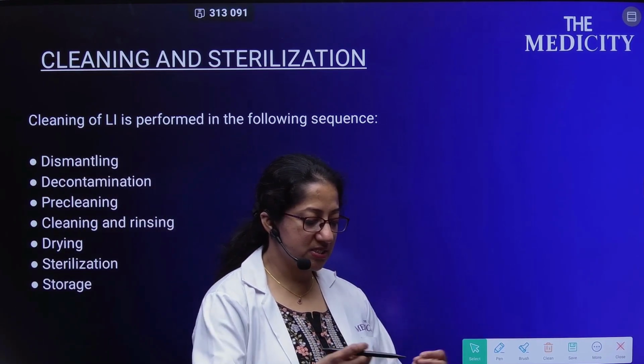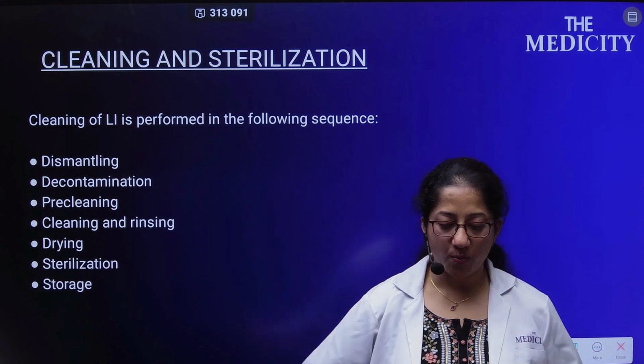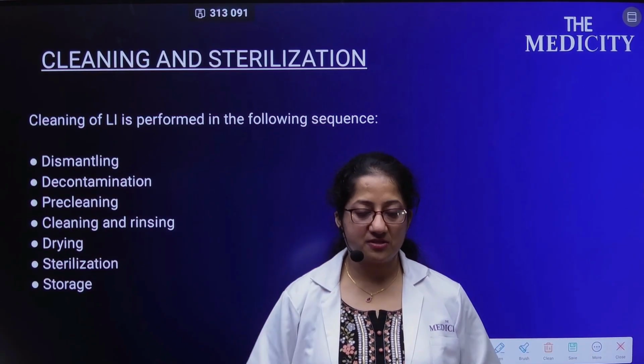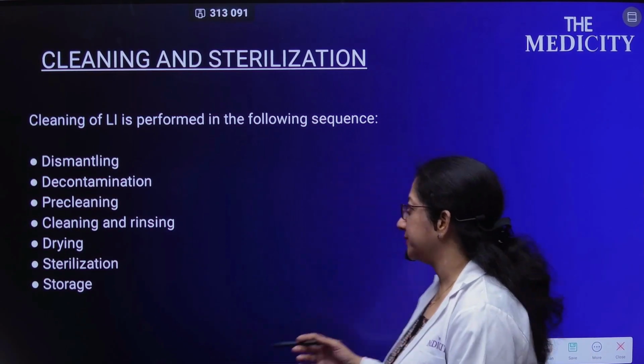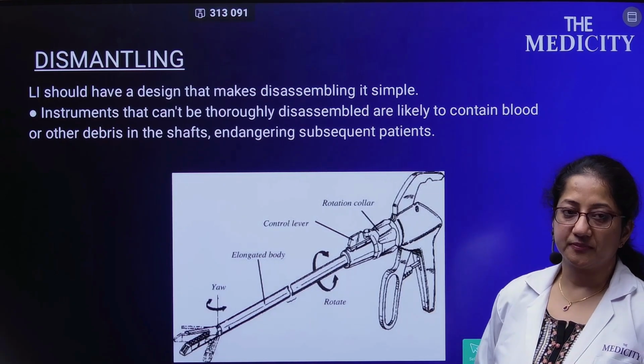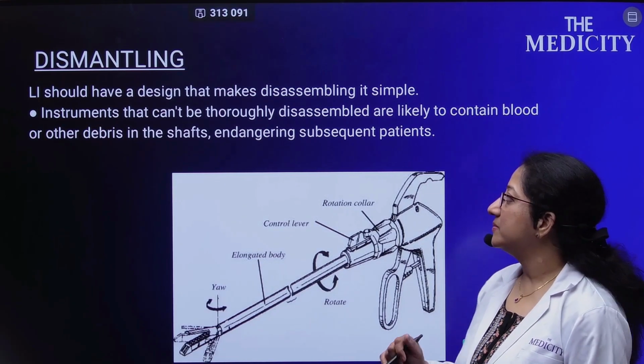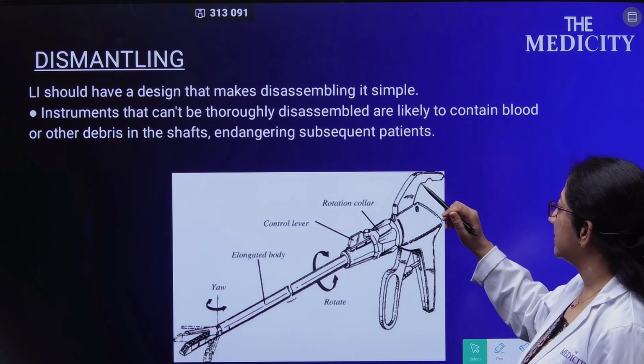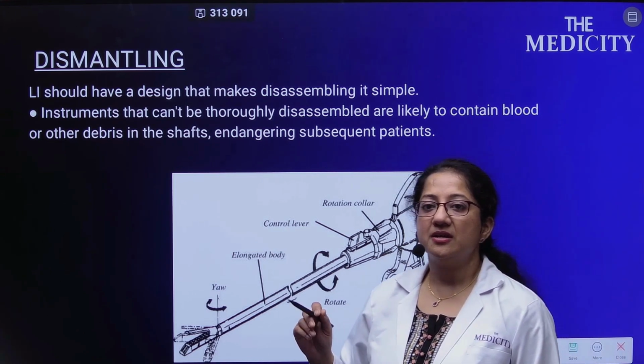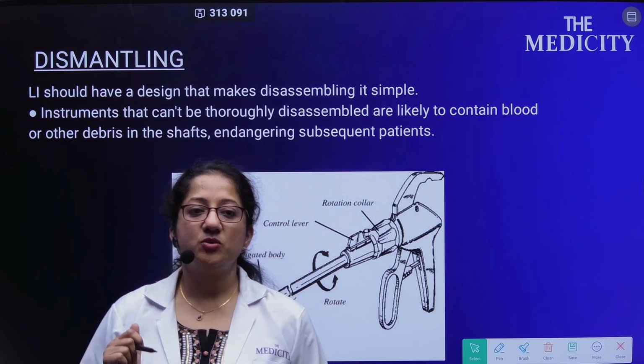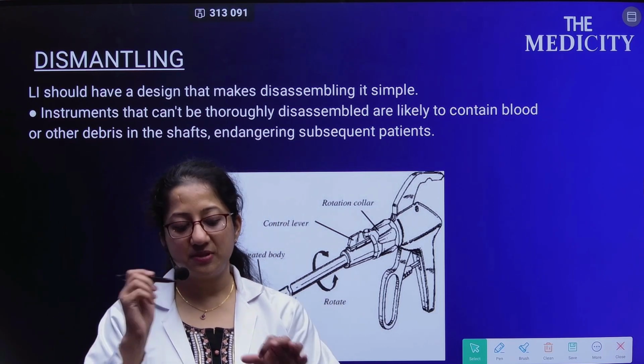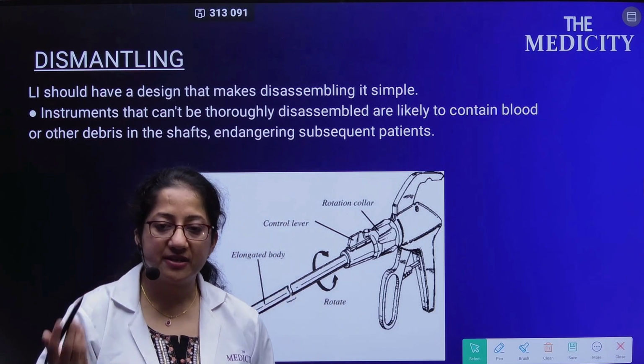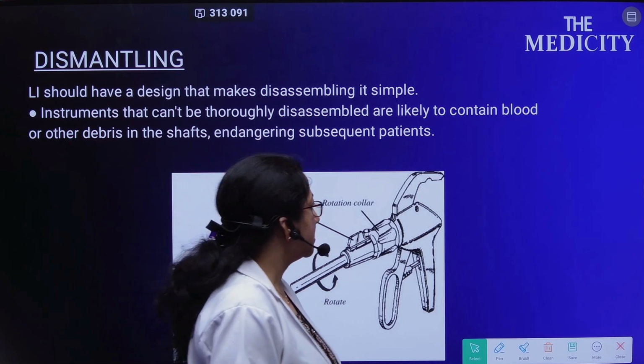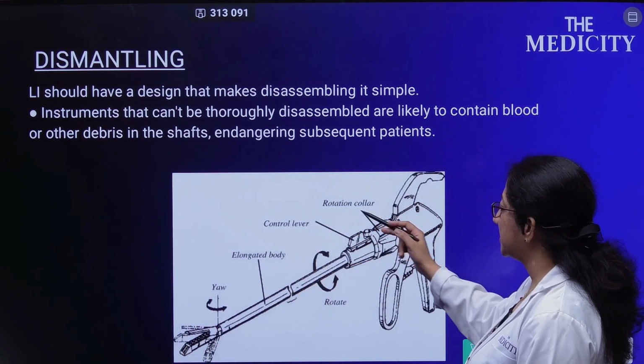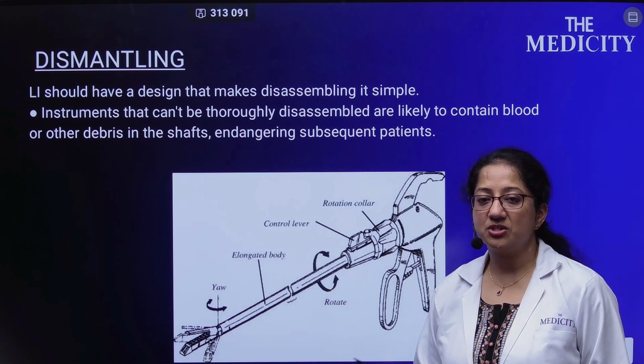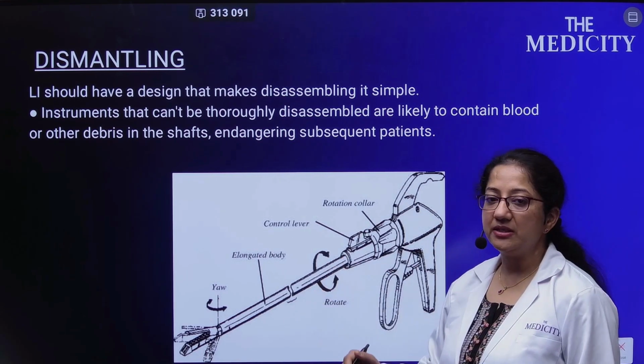Every instrument is dismantled after surgery, meaning it is opened and all the parts are separated and cleaned separately. So for dismantling, basically we should disassemble the instrument. If they can't be thoroughly disassembled, then they are likely to contain some blood clots or some debris which can be stuck in the shaft, which can endanger the safety of the subsequent patients. So every part of the instrument needs to be disassembled, which can be done by a trained technician in the OT, and then they need to be cleaned properly.